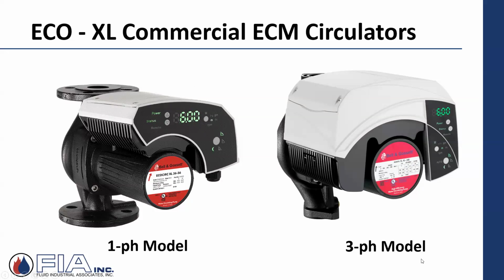Same thing, pumps coming with the motor and the drive mounted on board. It's got a printed circuit board, a microprocessor on board. It's got some intelligence, and it has its place. It's not the be all and end all, but when you're in that flow rate, BTU, chilled water, hot water capacity, or boiler plant, this has a nice application. It fits perfectly, and it provides you with either speed change or different applications.